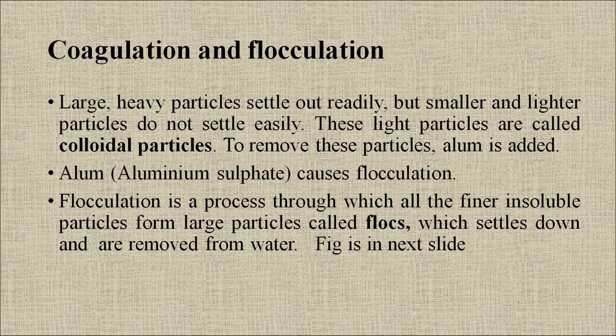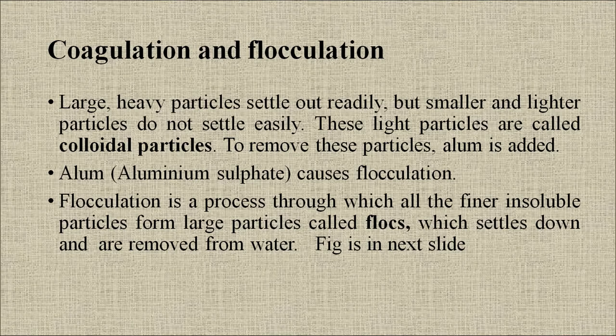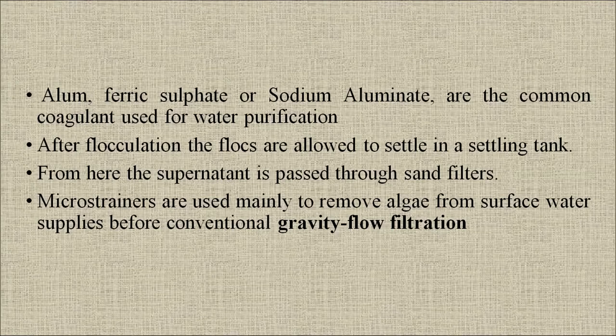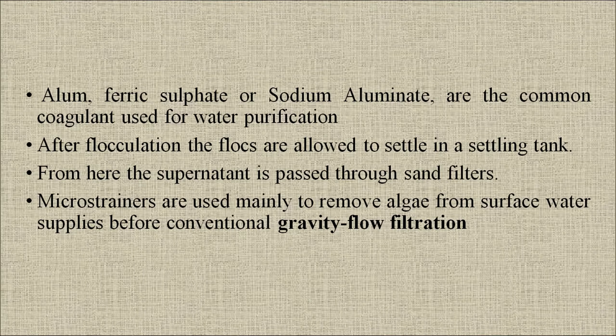Coagulation and flocculation: large, heavy particles settle out readily but smaller and lighter colloidal particles do not settle easily. Alum is used to remove these particles. Flocculation is a process through which finer insoluble particles form large particles called flocs, which settle down and are removed from water. Alum, ferric sulfate or sodium aluminate are the common coagulants used for water purification. After flocculation, the flocs are allowed to settle in a settling tank, and the supernatant is then passed through sand filters.